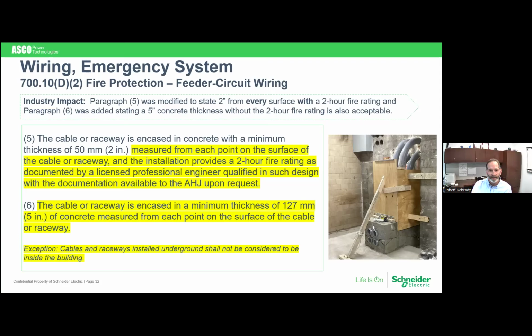So what they're saying now is if you're going to encase conduit and wiring within concrete, it's not good enough just to get a 2-inch coating from every surface. They also want a licensed professional engineer to confirm that this will ensure you have a 2-hour fire rating.